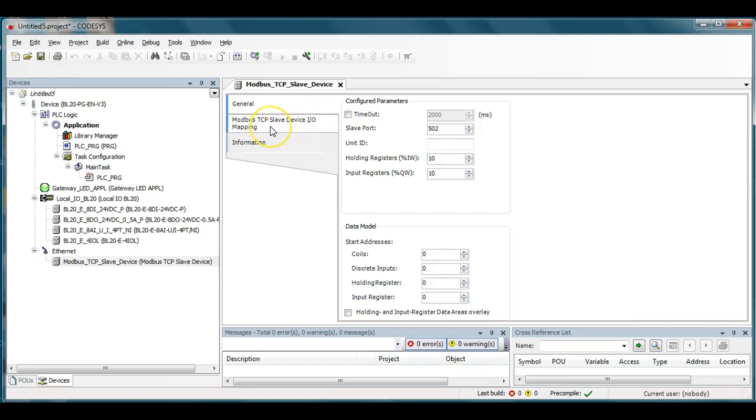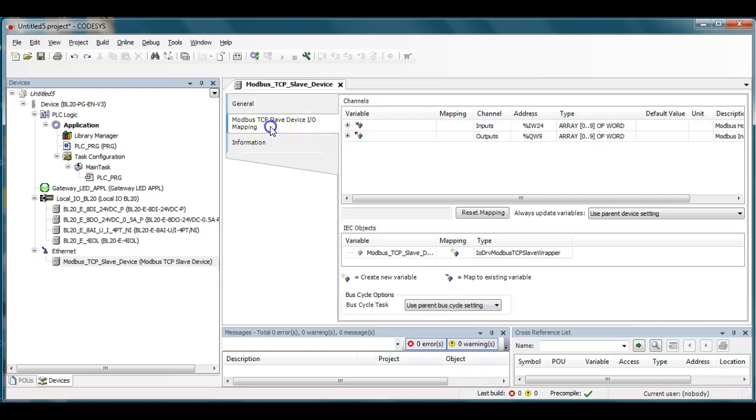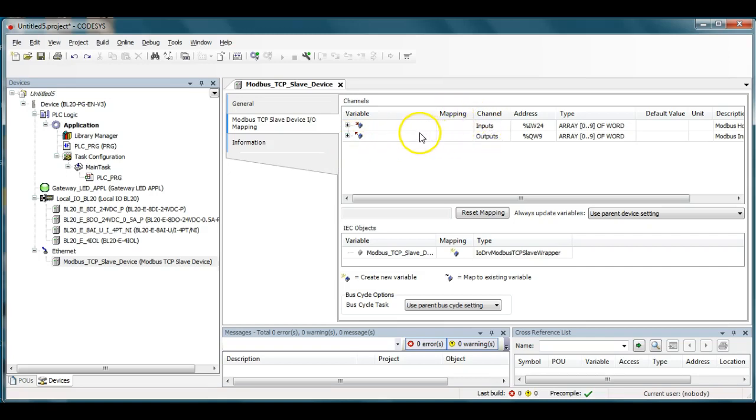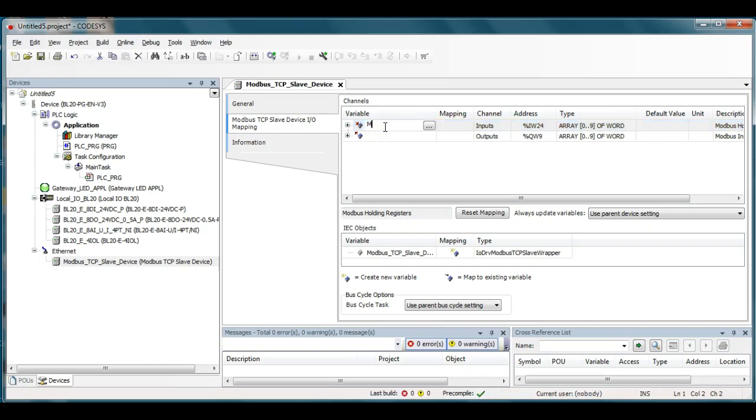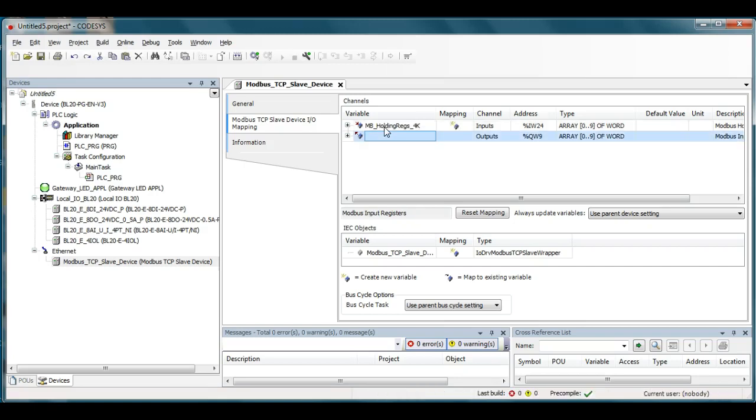Now under Modbus TCP mapping right here, this is what I'm getting at here. The inputs here are what is coming into the particular BL20 and these are actually from the master will be the holding registers. So what I'm going to do here I'm going to go ahead and name this Modbus underscore holding regs registers and then underscore 4k because these are the 40000 series that are inputs coming into the Turk device here.